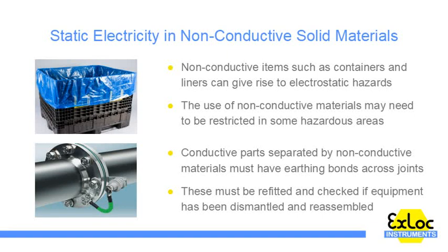It is good practice to minimize the use of non-conductive materials in hazardous areas, and today many formerly non-conductive materials are available in versions which allow electrostatic to dissipate to earth, and these are known as static dissipative or sometimes antistatic materials. Choosing static dissipative materials over their non-conductive equivalents will greatly improve the ability to control static.